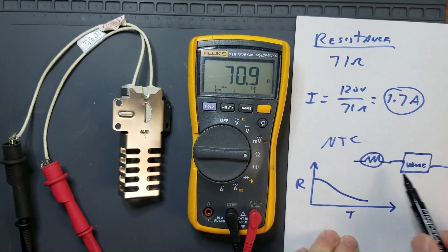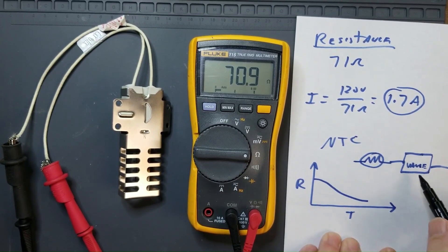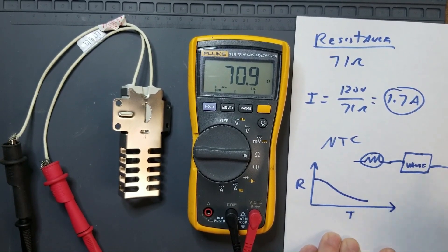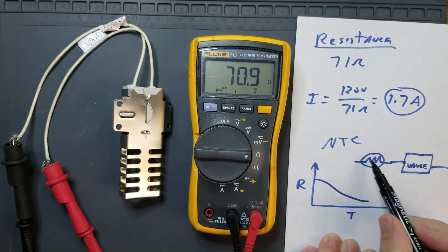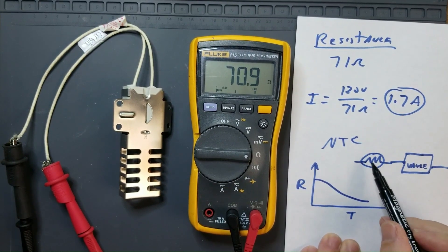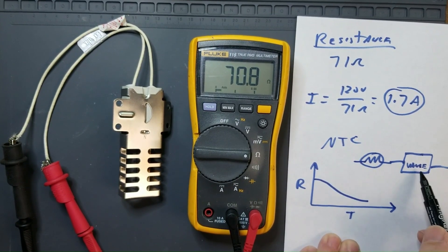That increase in current reaches the threshold and opens the valve. That tells the valve that the igniter is drawing enough current to be hot enough to light the gas.